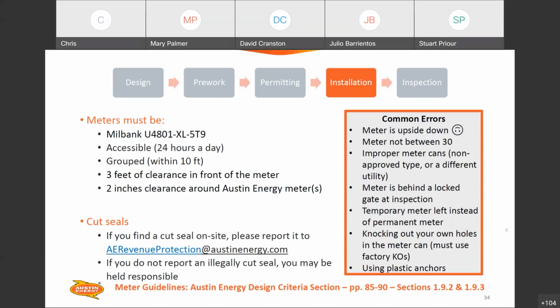Knocking out your own holes in the meter can: you have to use the factory knockouts. Don't make your own holes in those meter cans. The metering department will reject that and it will not set the meter. Also, specifically in the meter cans, don't use plastic wall anchors. They're just not long lasting. They need to be something rigid, something like Tapcons or an appropriate fastener for whatever wall you're working with.